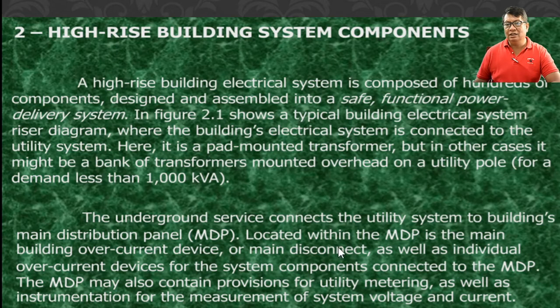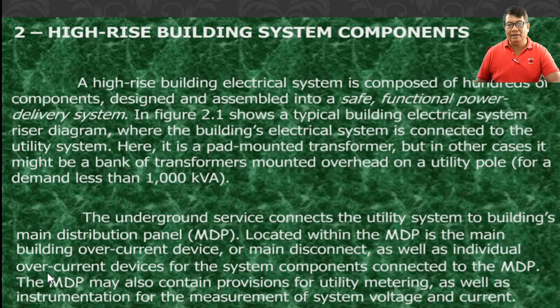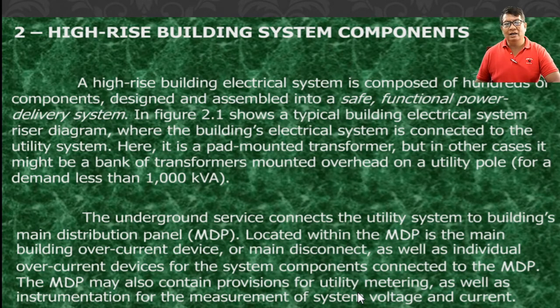The MDP — main distribution panel — is the key distribution point. Located within the MDP is the main building over-current device or main disconnect, including individual overcurrent devices. When we see overcurrent devices, we have two types: fuses or circuit breakers. The MDP may also contain provisions for utility metering — the mother meter used by distribution utilities for a single metering point.